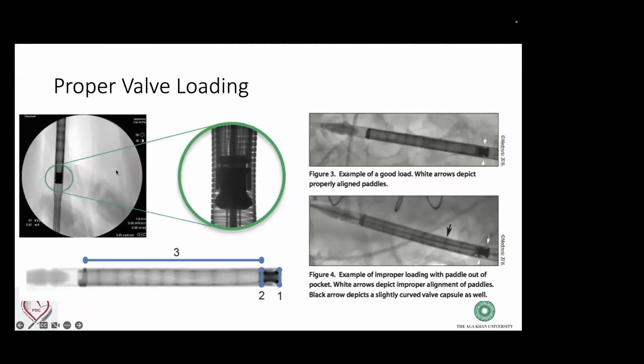When the valve is handed off to you, you're going to inspect it under cine, 30 frame cine, and look at the paddles. The paddles should be symmetrical. The valve should be straight. There should be no dissymmetry or asymmetry in the valve.